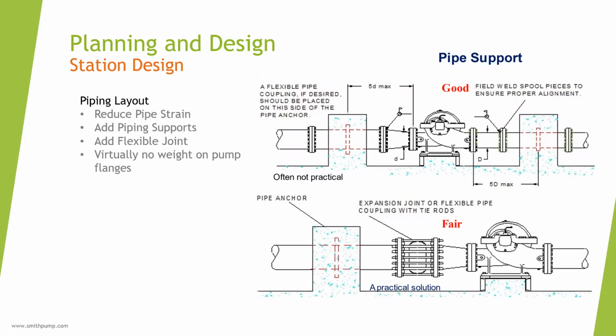The top drawing anchors all piping near the pump for maximum support. This allows the concrete block to support the pipe weight, not the pump. Final flange to flange alignment requires field welding the pipe in this example. Since field welding is somewhat impractical, the bottom picture is more commonly found at job sites.